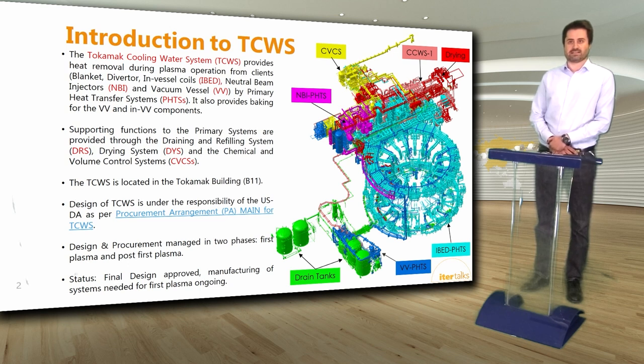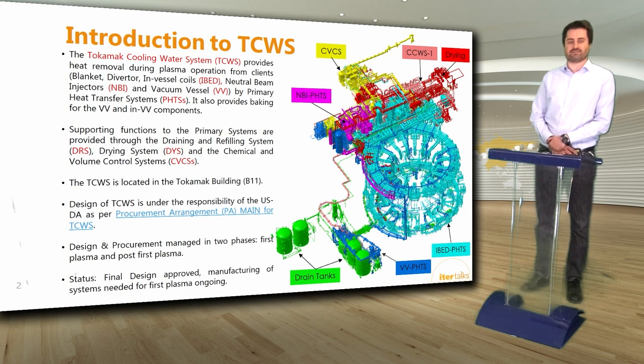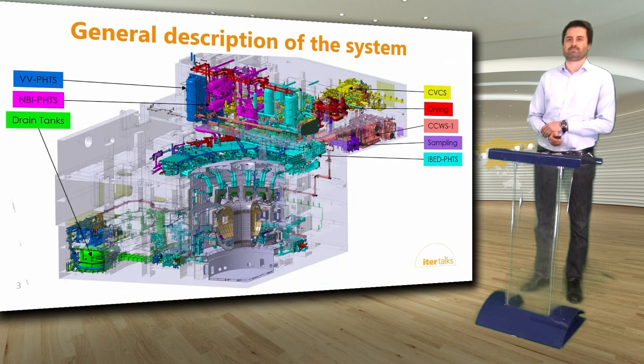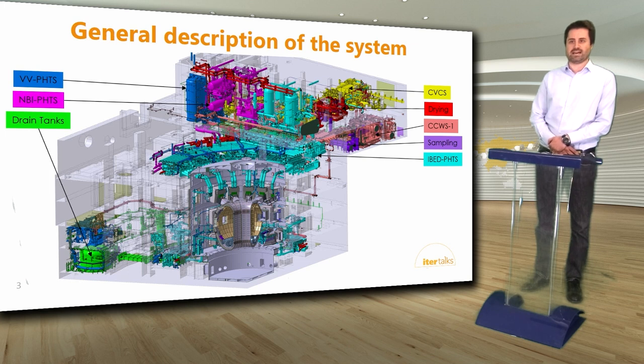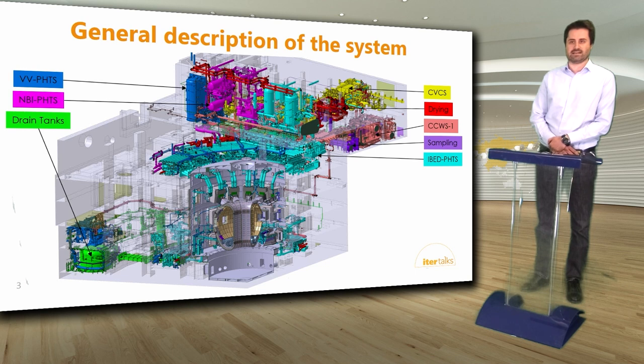In addition to these three main systems we have auxiliary or supporting subsystems: the chemical and volume control systems, which control water chemistry and water volumes of the main subsystems; the drying system, which dries out the in-vessel components and vacuum vessel prior to long-term maintenance; and the draining and refilling system, which drains the main systems prior to maintenance and refills them once maintenance is finished. The TOKAMAK cooling water system is completely located in the tokamak building and nuclear building of the ITER machine. Design and procurement is the responsibility of the United States domestic agency, managed in two main phases.